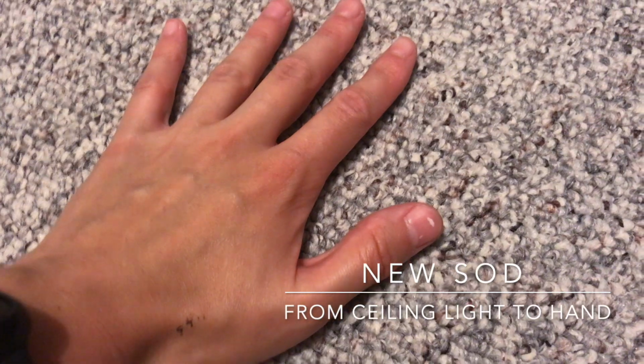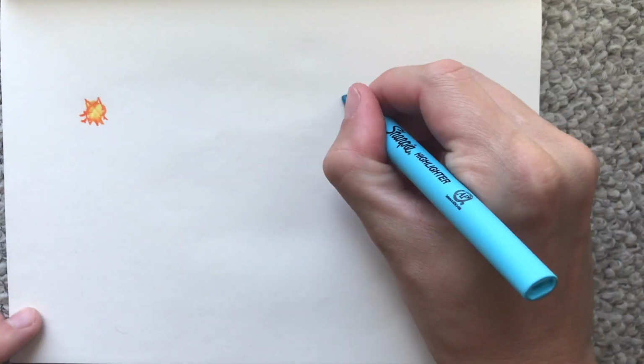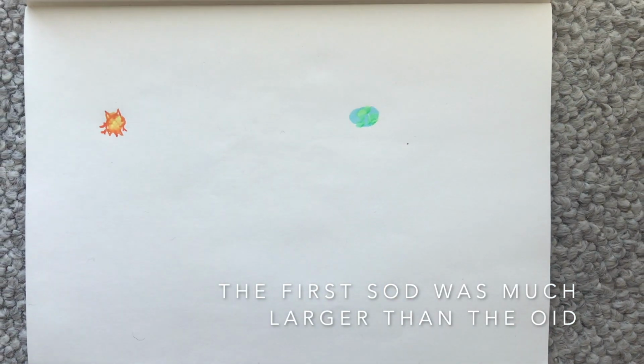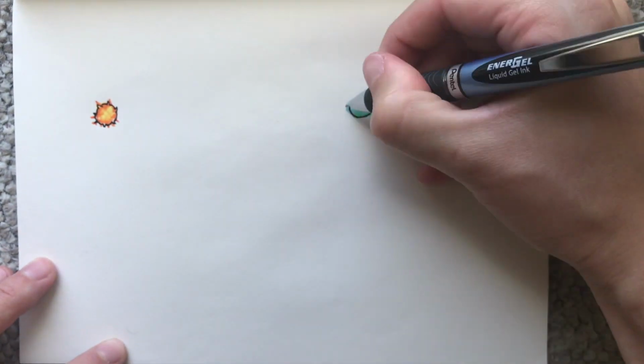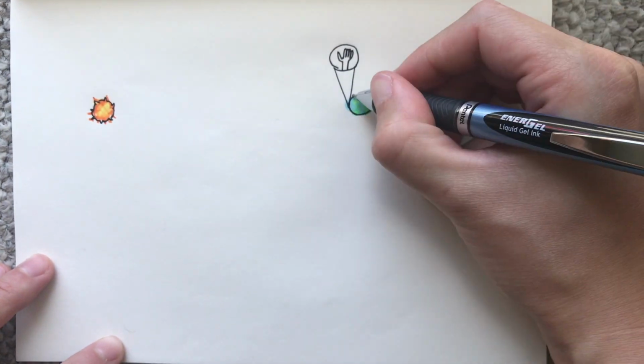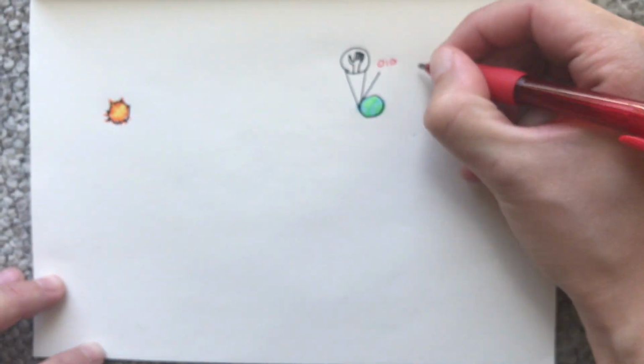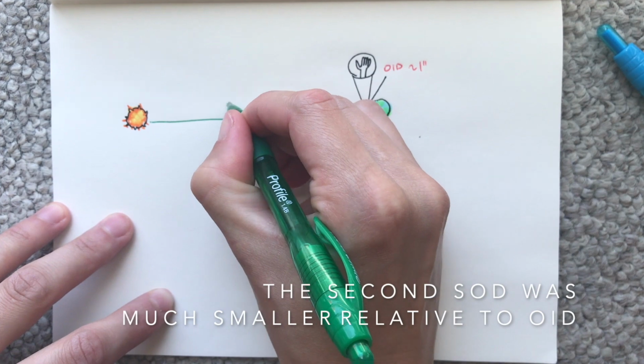Now I'm reducing my SOD by using a ceiling light. This time, changes in OID result in much more noticeable blur. The reason is that I've changed the ratio of SOD to OID. Outside, my SOD, the distance from the sun to my hand, was so big that changing my OID didn't make a drastic difference. My second SOD from the ceiling light is so much shorter that small changes in OID resulted in a lot more blur.